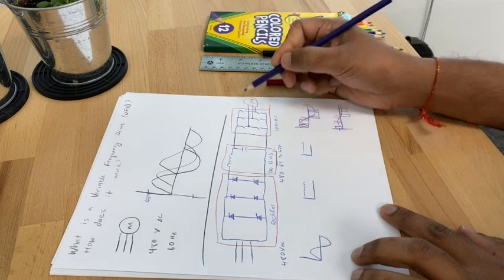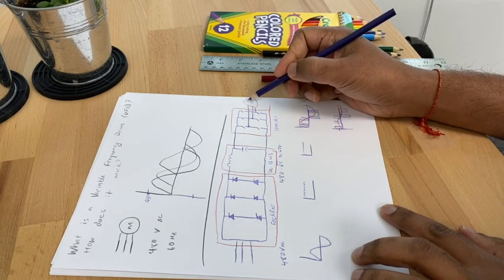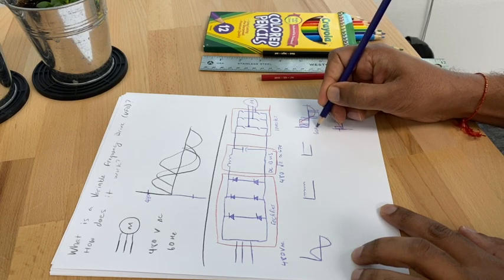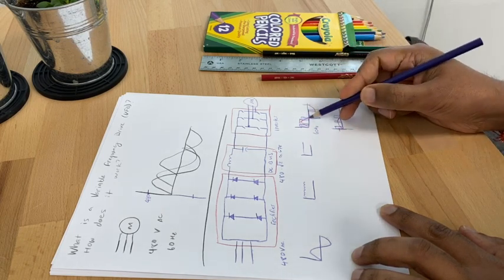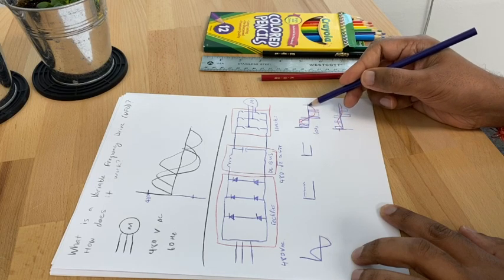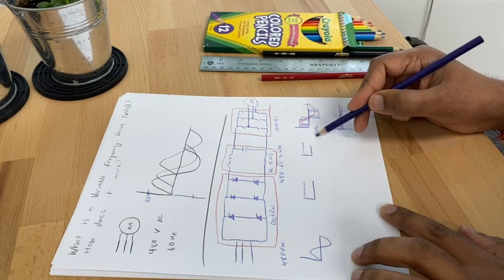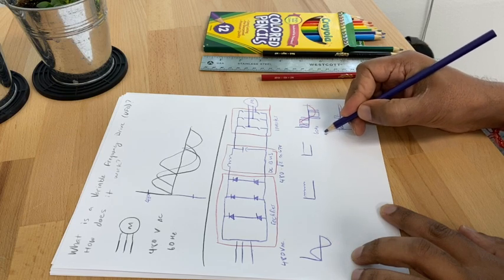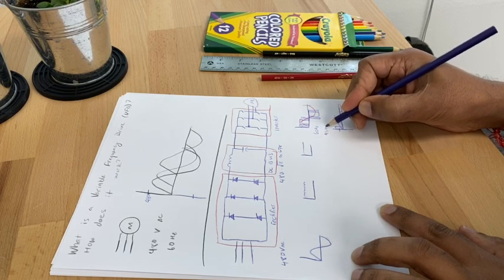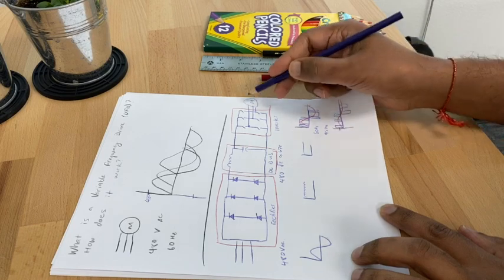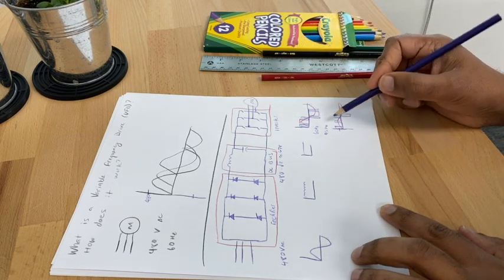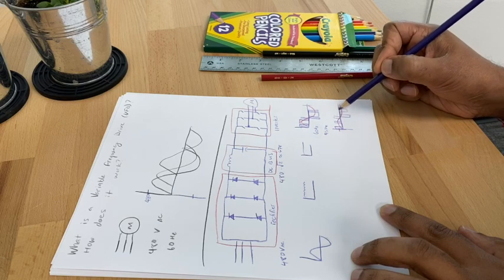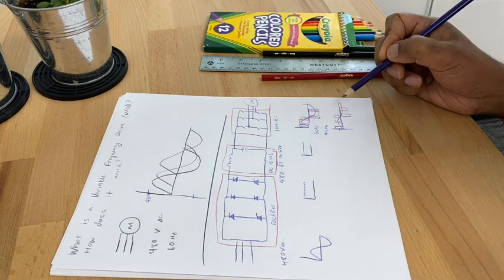Most motors operate at 60 hertz, at least in the US. If we were to change that frequency down to, say, 45 hertz, it would proportionally reduce the speed of the operating motor. And by changing the voltage, we're able to adjust the torque going into the motor. There's a lot more to it than that, but at a high level that's a brief explanation.